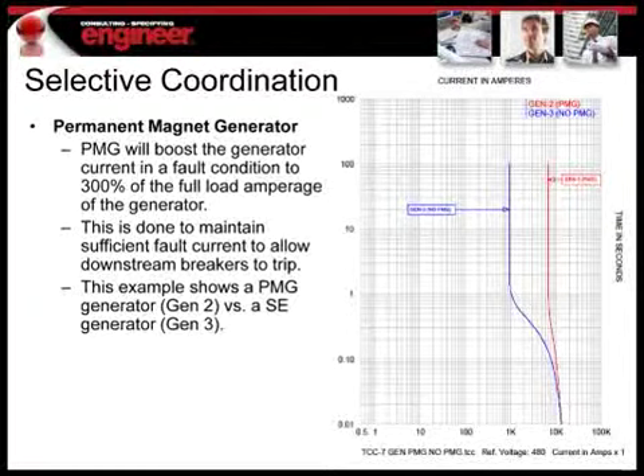Okay, so back to the PMG. The benefit of a PMG from a coordination standpoint is that the PMG will boost your fault current during a fault event to 300% of your full load amps. If you look at this TCC, we have 2 identical generators, one with PMG and one without PMG. As you can see with the blue line, which is the non-PMG, it starts out at the same level, but it decays very rapidly. And when you're talking about selective coordination and allowing the breakers to trip downstream, you want to make sure that you maintain a certain amount of fault for those breakers to react to. So the PMG on the system is pretty important from that standpoint. We typically specify PMG for all of our healthcare and larger jobs, and I know most manufacturers typically standardize around PMG on the larger engines.